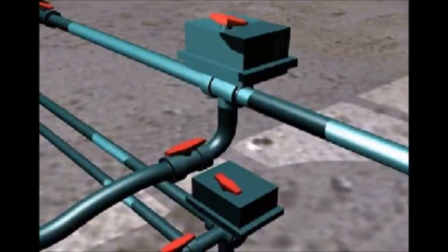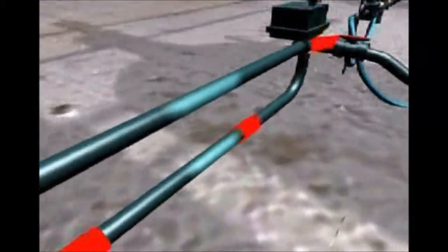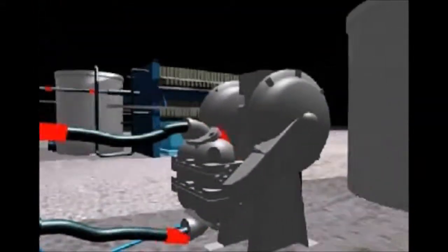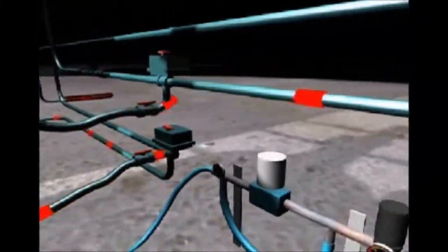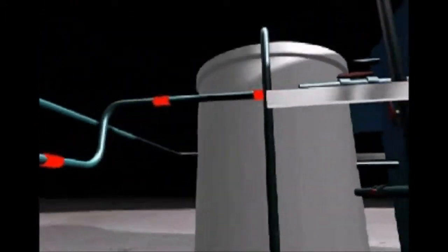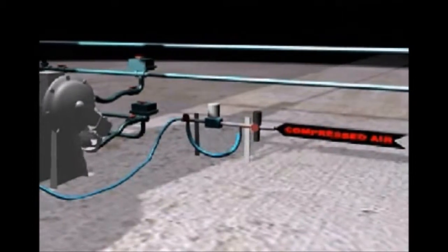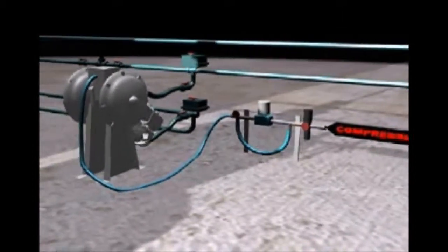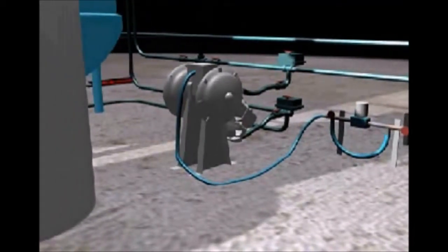This activates the phase of sludge transfer to the filter press, starting with the activating of three-way valves that allow the pump to draw sludge off the bottom of the tank and transfer it to the filter press. With this phase, the dewatering of the sludge begins. In the dewatering phase, the sludge pump works through several increments of pressure of sludge transfer to the filter press. This is controlled through monitoring the sludge pump with a stroke monitoring device and transducer controlled by the PLC.